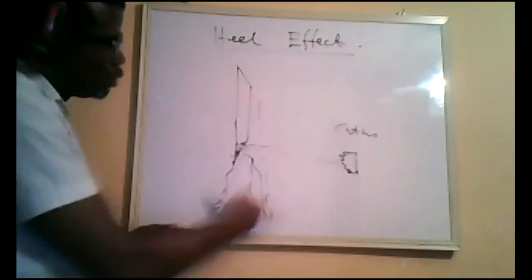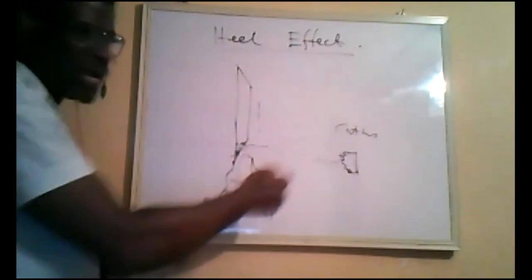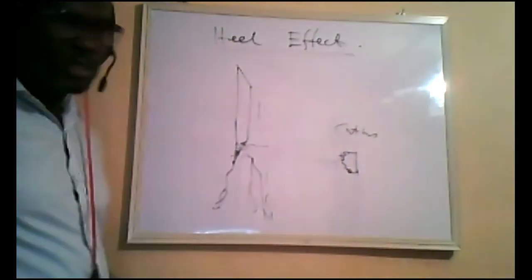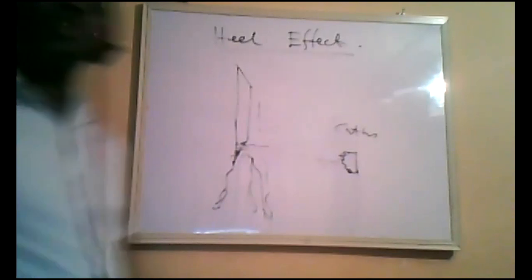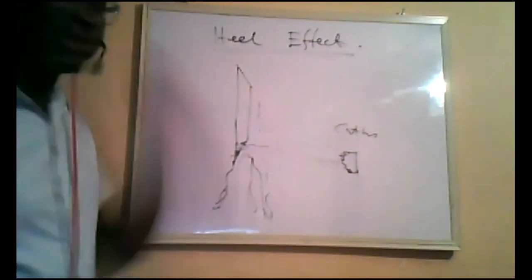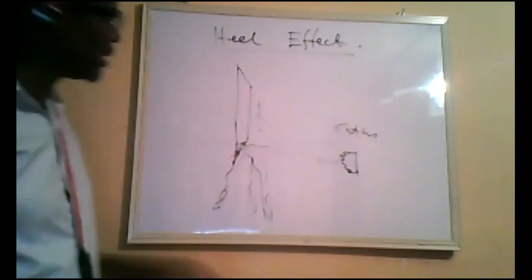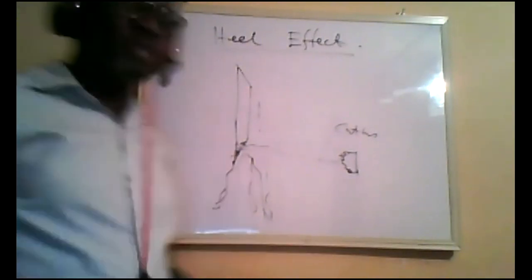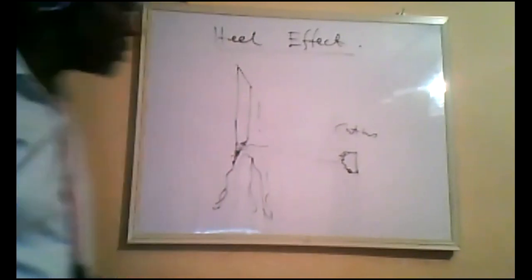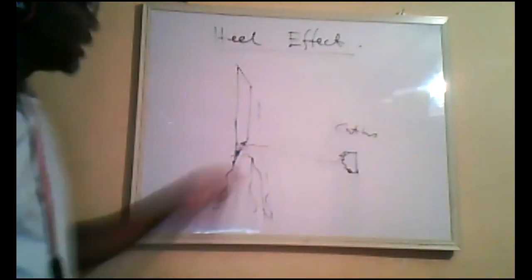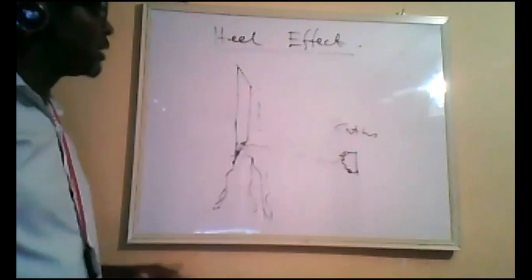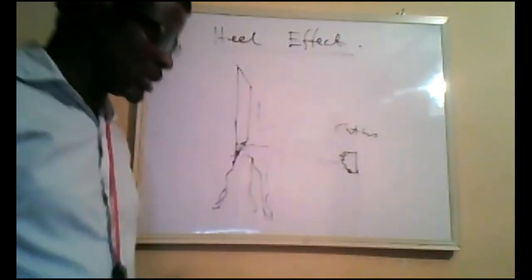As you move down inside the anode, the X-ray beams emanating from there continue to have reduced energy, because the photons coming out from there are going to be much more attenuated than the ones around this area. It is a form of problem in radiography, but it can also be used to our advantage.